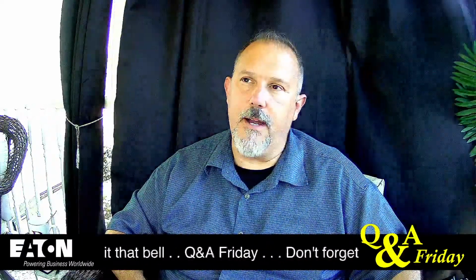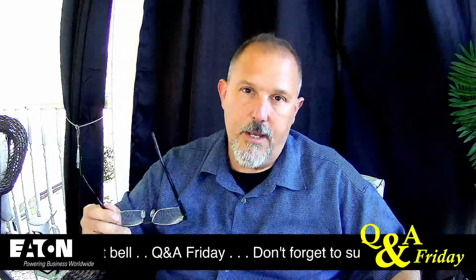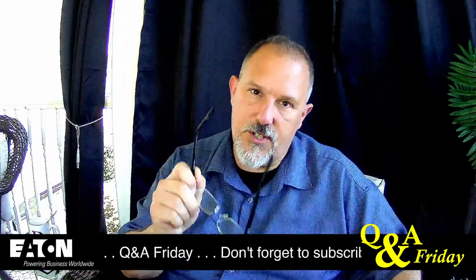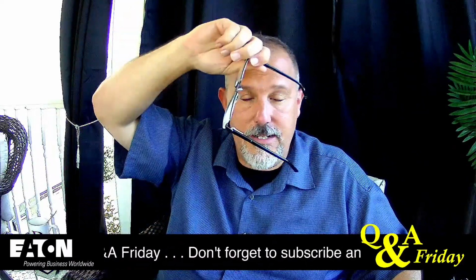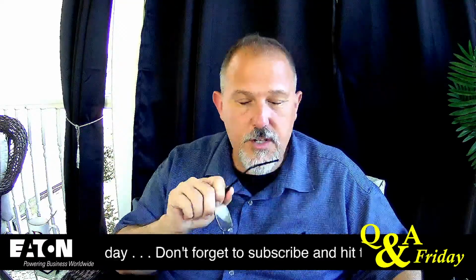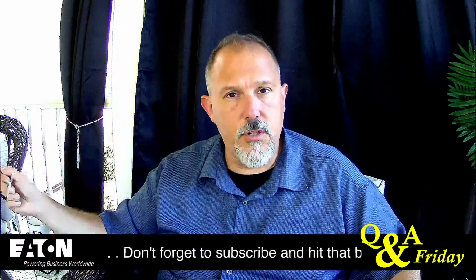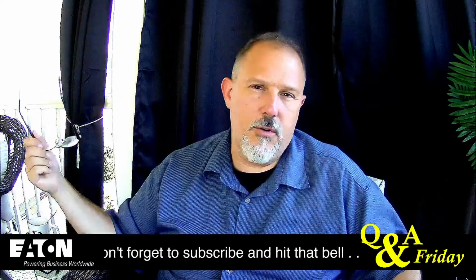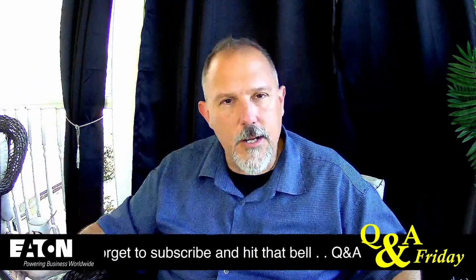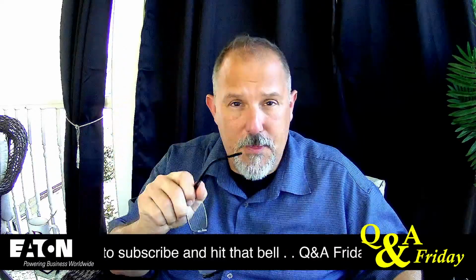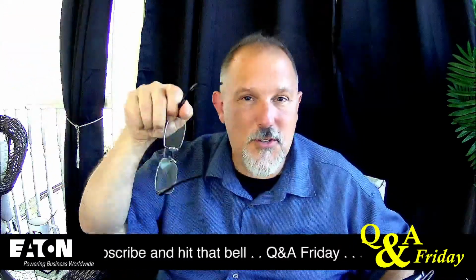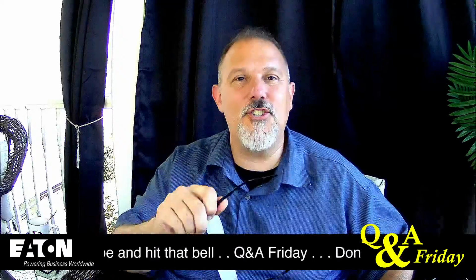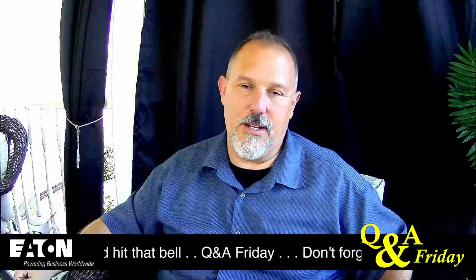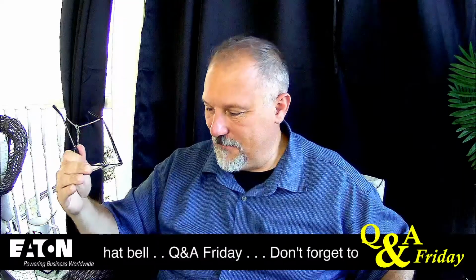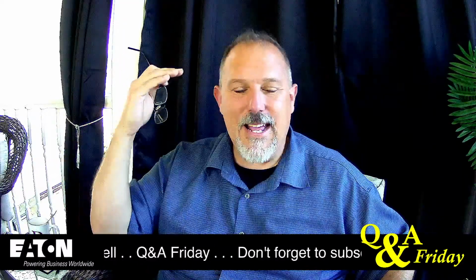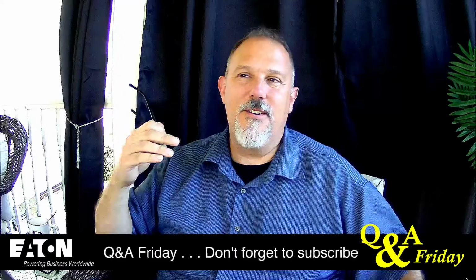Oh my gosh. So I phoned a friend and it was 250.24C because it's on the line side of the service. And if you look at 250.24C, it tells you need to pull that neutral to the first switch or panel or whatever it is. In this case, it's a fire pump controller. And you got to think, if you're coming from the utility, the utility is always going to give you that neutral, and that neutral is what's going to get you your fault return path back to the utility. But for some reason, I had that problem of trying to tie that code section.